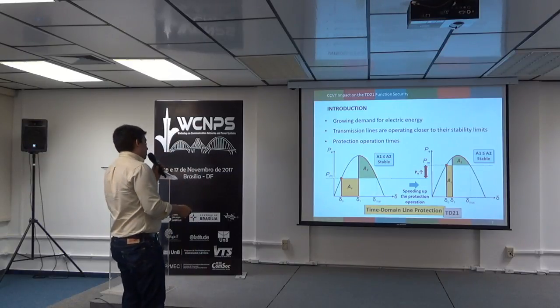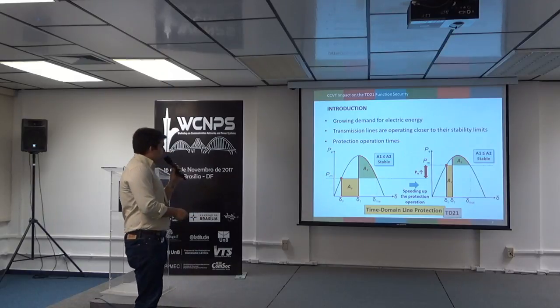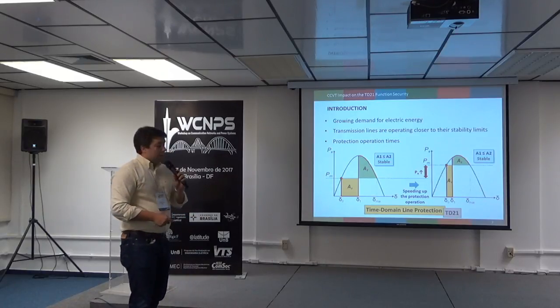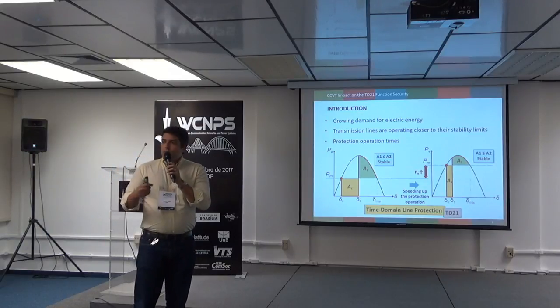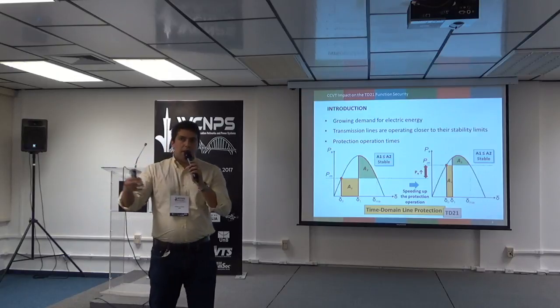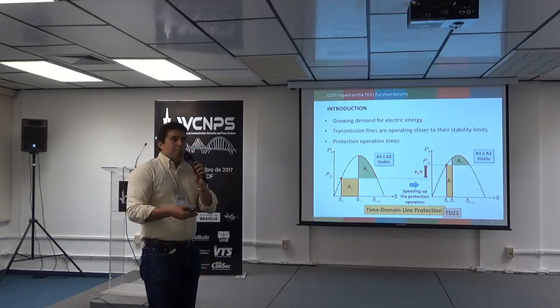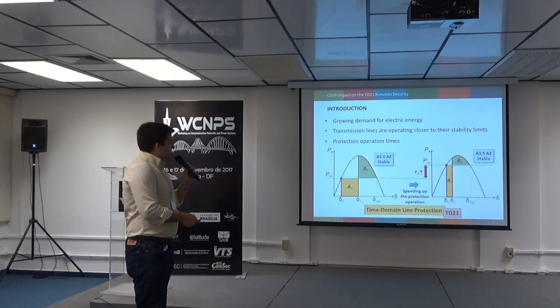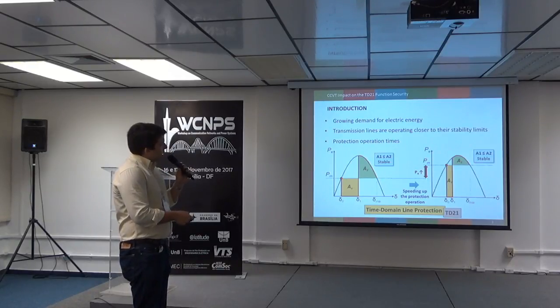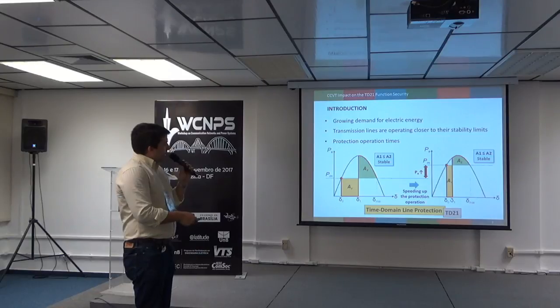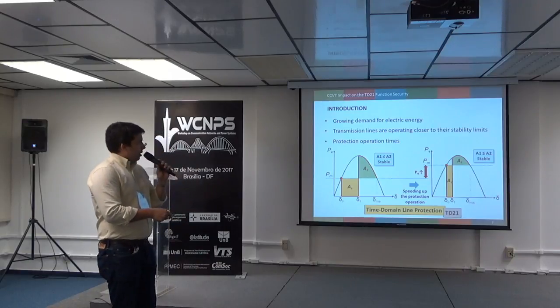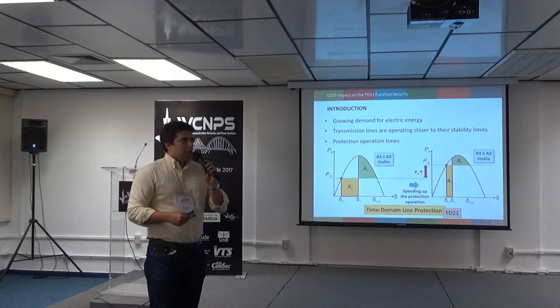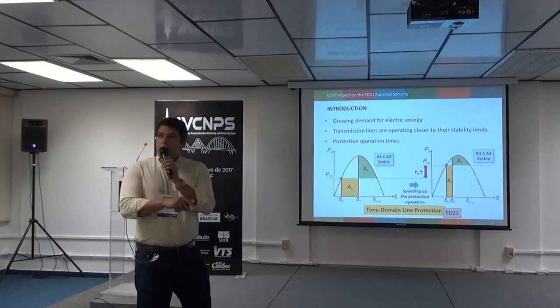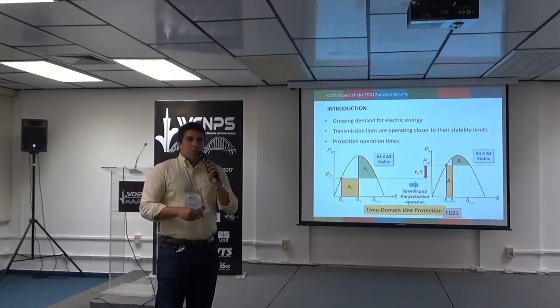In this case, we have to define this point of operation based on the time to operate of these protection functions. But since we need to transmit more and more power over the transmission lines, we want to speed up this protection. If we speed up these protection functions, we have the chance to increase the electric power transmitted in transmission lines. So if I have the same severe short circuit, but my protection operates faster than the phasor-based one, I will not have problems in this case. And in this scenario, the time domain protection function has shown to be very promising.